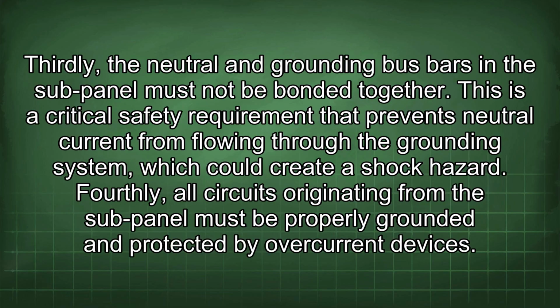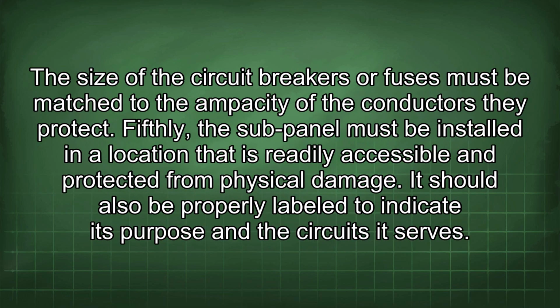Thirdly, the neutral and grounding bus bars in the sub-panel must not be bonded together. This is a critical safety requirement that prevents neutral current from flowing through the grounding system, which could create a shock hazard. Fourthly, all circuits originating from the sub-panel must be properly grounded and protected by overcurrent devices. The size of the circuit breakers or fuses must be matched to the ampacity of the conductors they protect.